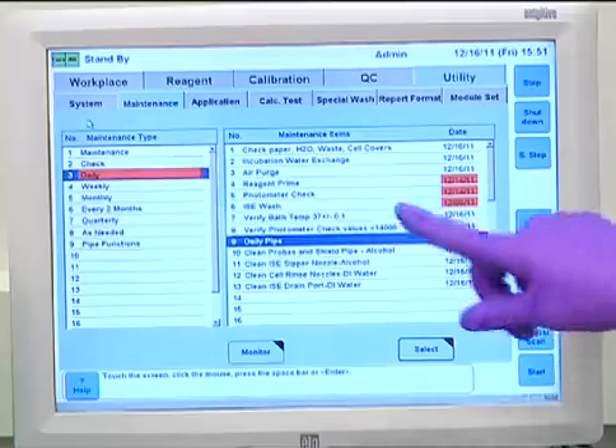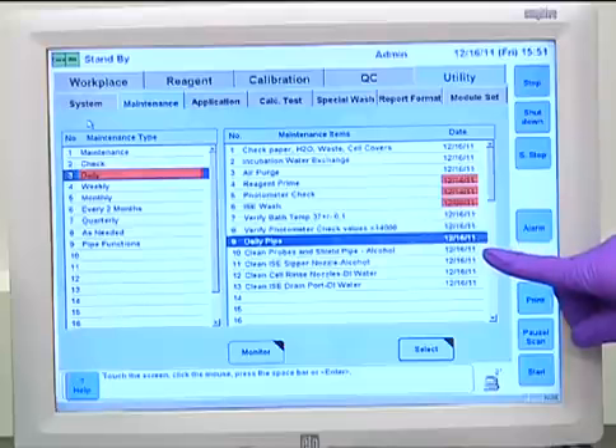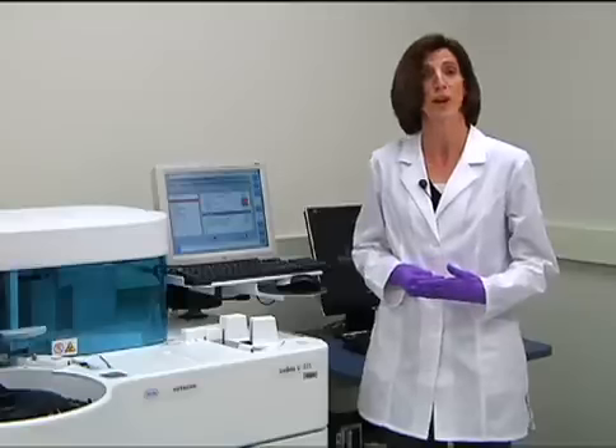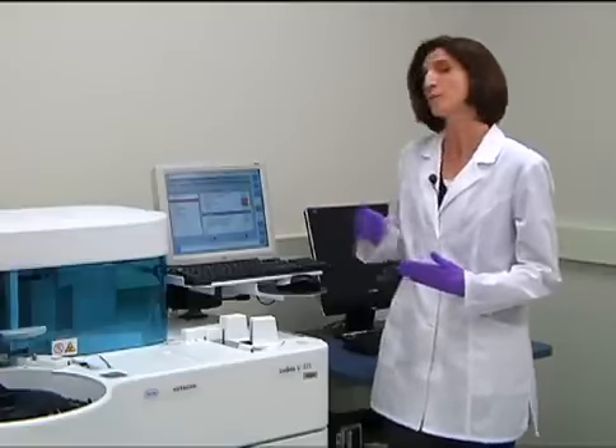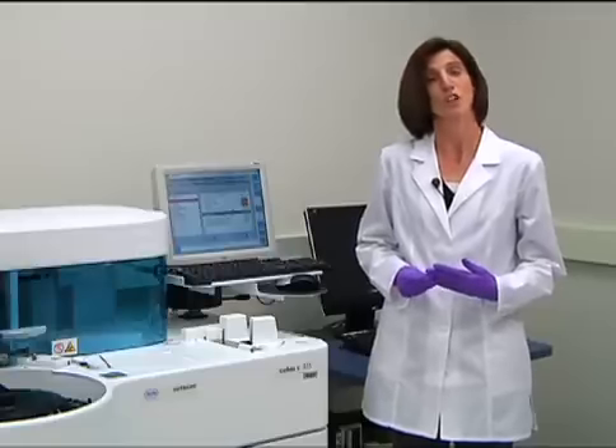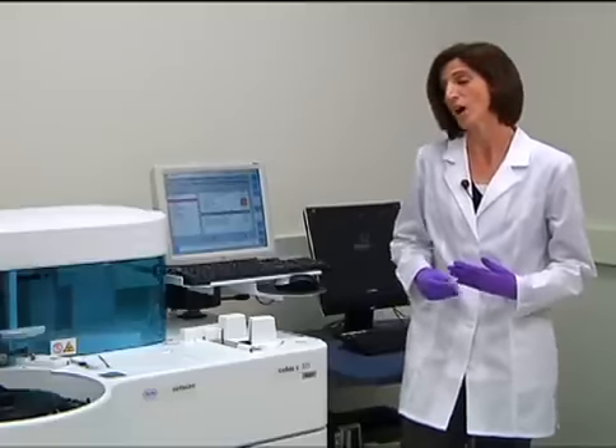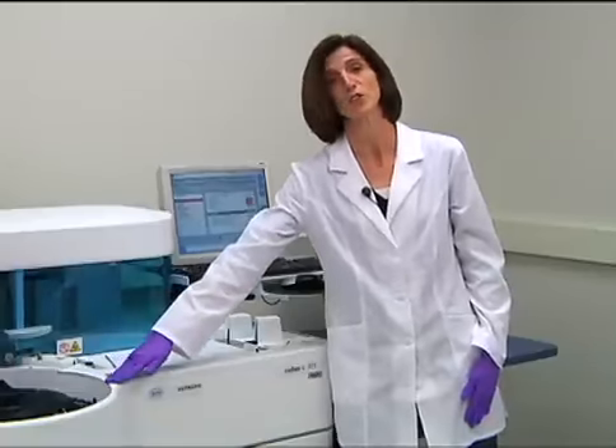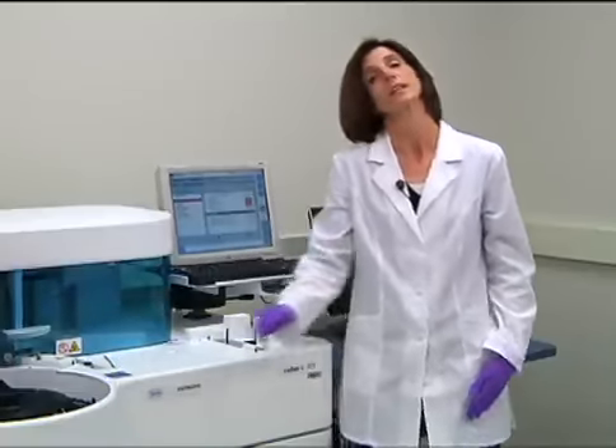And what we will perform will be something called a daily pipe. A pipe is just a way to execute individual maintenance items one right after another. So by a simple push of the button, I'm able to execute all of the daily maintenance. Items included in the pipe include a bath exchange, an air purge, a photometer check, an ISE wash, which will require 2 cleaning solutions on the sample disc. In addition, if your lab runs drugs of abuse, you will need to run a wash reaction parts, which could also be included in the pipe.